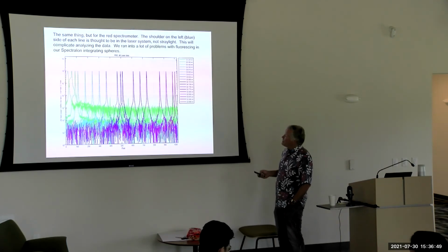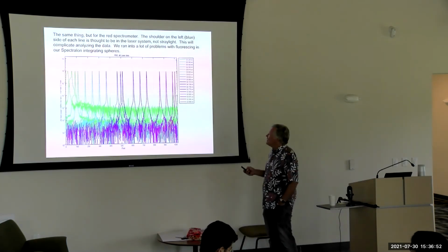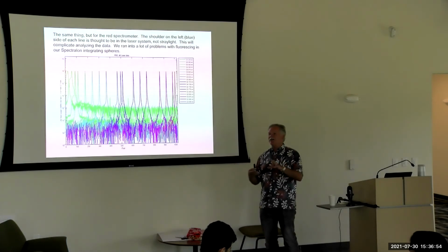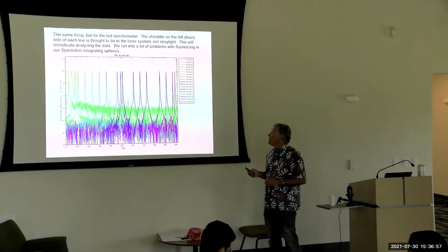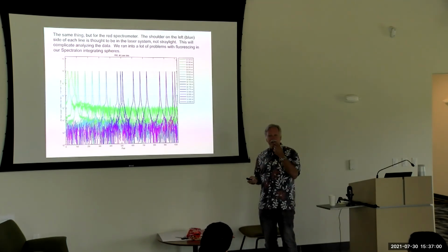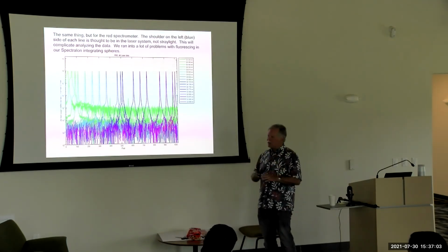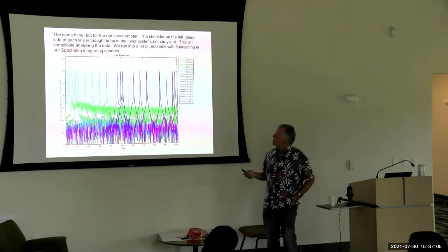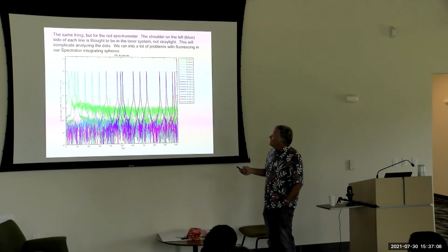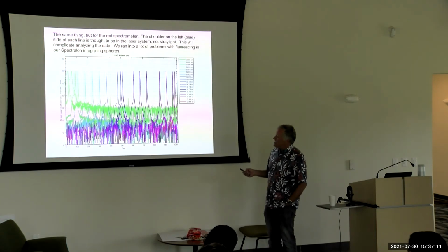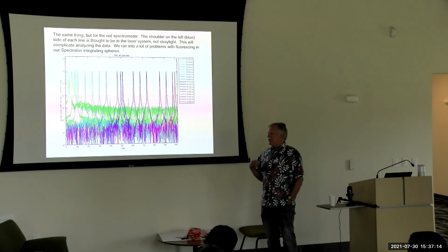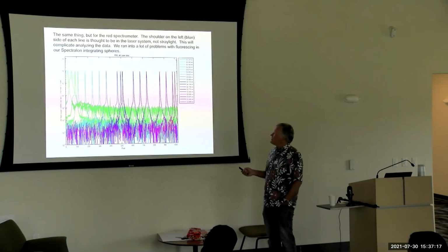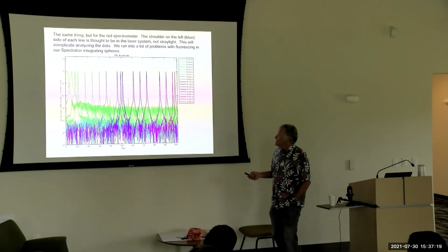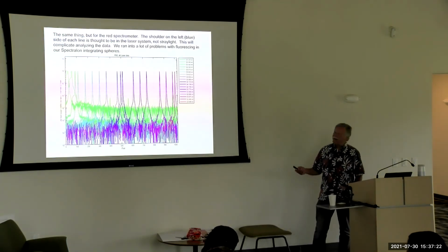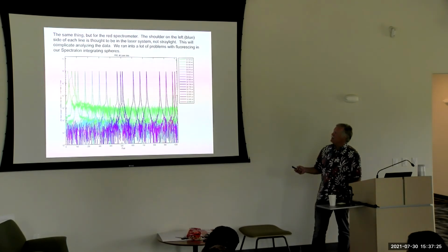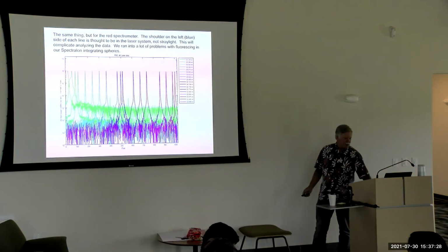We ran into a lot of problems that stopped us for a while. Fluorescing: the laser light comes into an integrating sphere, and we sampled that. And the Spectralon was fluorescing a lot and causing a broadband thing that looked like stray light, but it turned out, we did a whole bunch of tests and figured out, it was the Spectralon. So we had to figure out how to illuminate the detectors uniformly enough that we could get away without the integrating sphere. So we're doing that now to try to simplify. But it is something to remember if you're using Spectralon, that it will fluoresce if it's not perfectly clean.